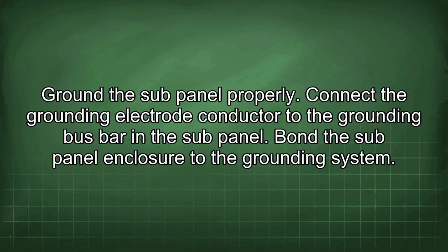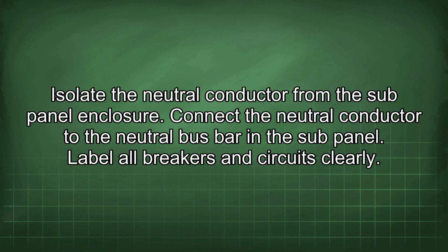Ground the sub-panel properly. Connect the grounding electrode conductor to the grounding bus bar in the sub-panel. Bond the sub-panel enclosure to the grounding system. Isolate the neutral conductor from the sub-panel enclosure. Connect the neutral conductor to the neutral bus bar in the sub-panel.